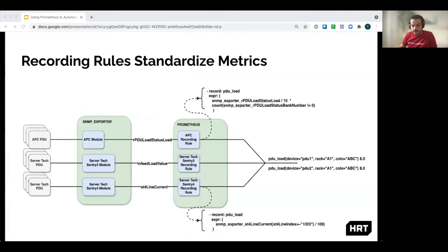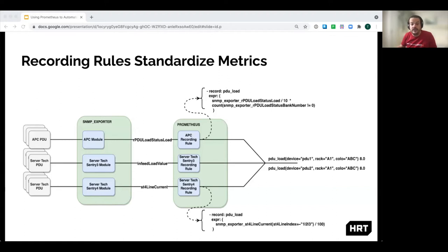So this should be simple, right? In an ideal world, yes, this should be simple. The first step to tracking power usage is easy: point the SNMP exporter at the PDUs, and we know how much power is being used there. But where the trouble comes in is we have multiple PDU vendors. With multiple PDU vendors come multiple SNMP MIBs, which result in multiple metrics. So the way a PDU displays power load is different across the vendors. One PDU vendor may display the total load of the PDU in amps, another in tenths of amps, and while another, we may need to sum multiple metrics to get the total load on that PDU.